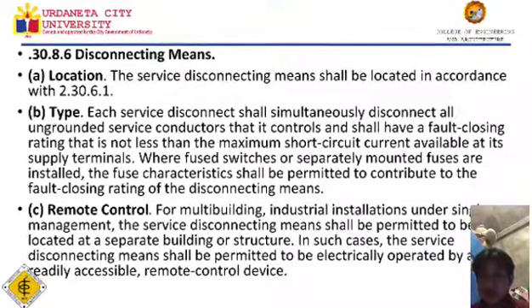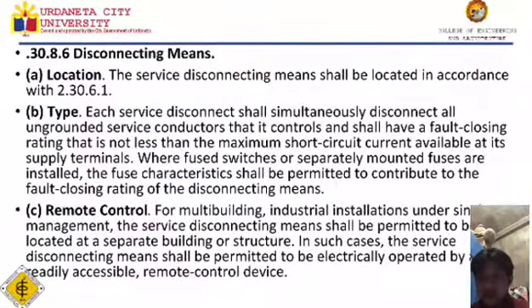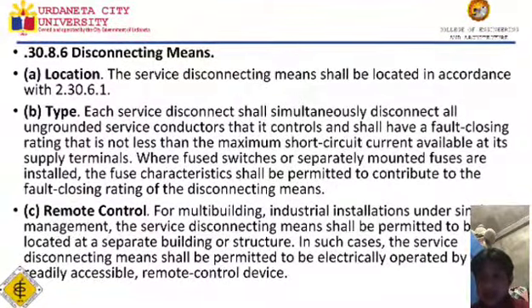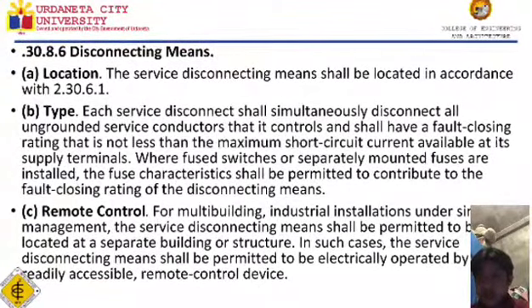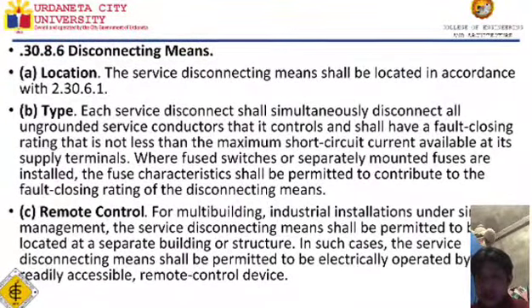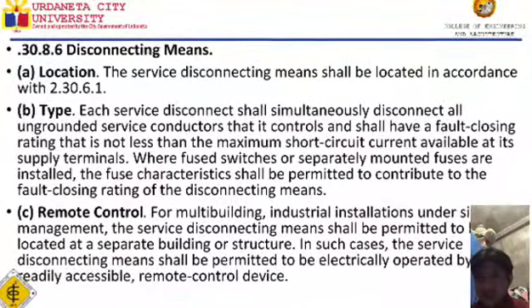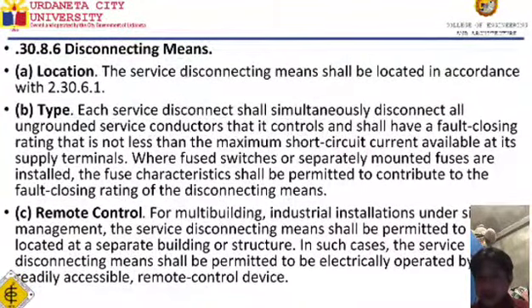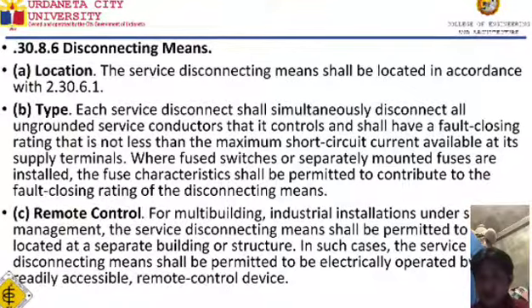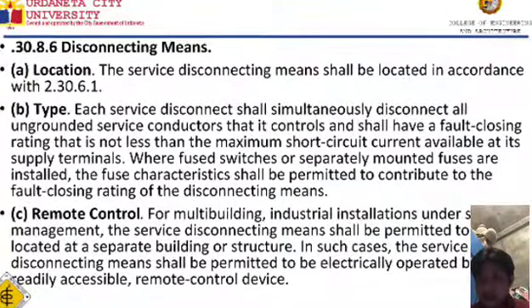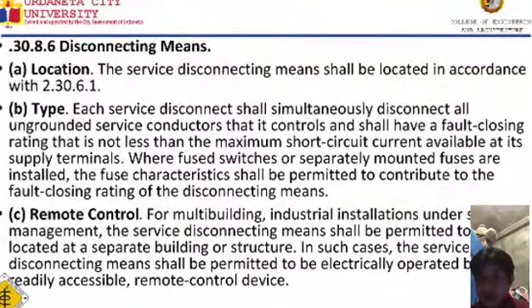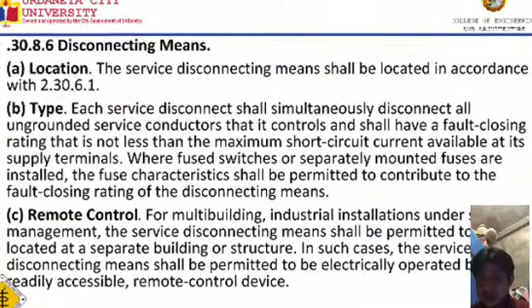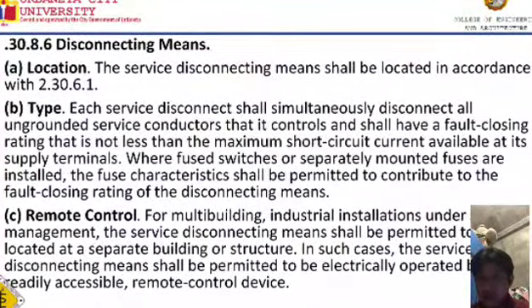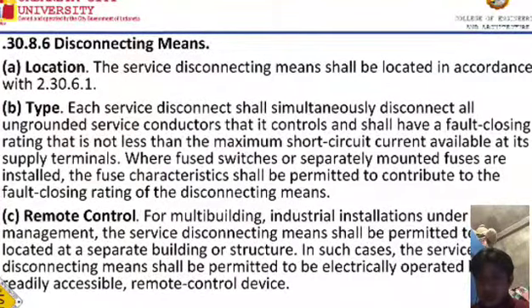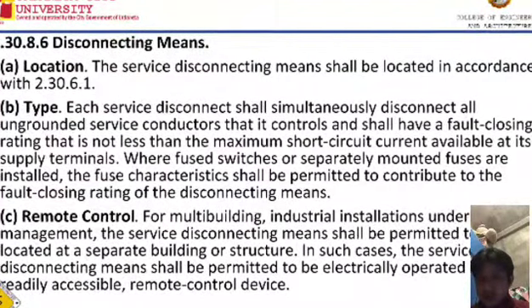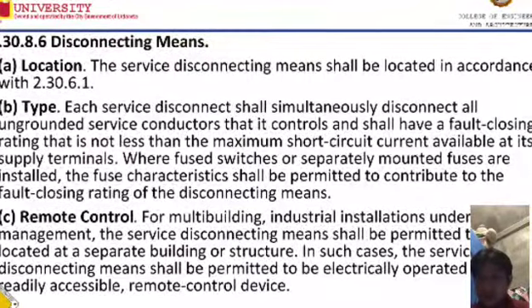Tapos letter B, each service disconnect shall simultaneously disconnect all ungrounded service conductor that it control and shall have a fault closing rating that is not less than the maximum short circuit current available at its supply terminals. Where fuse switches or separately mounted fuses are installed, fuse characteristics shall be permitted to contribute to the fault closing rating of the disconnecting means.